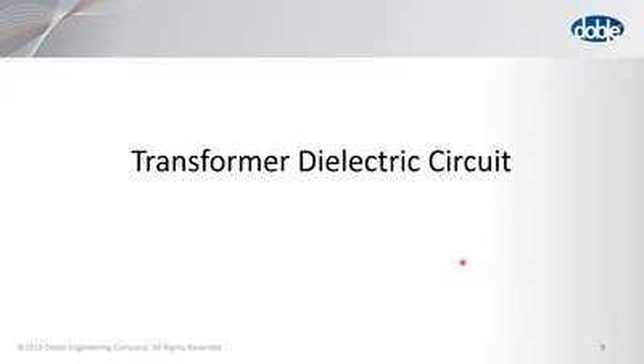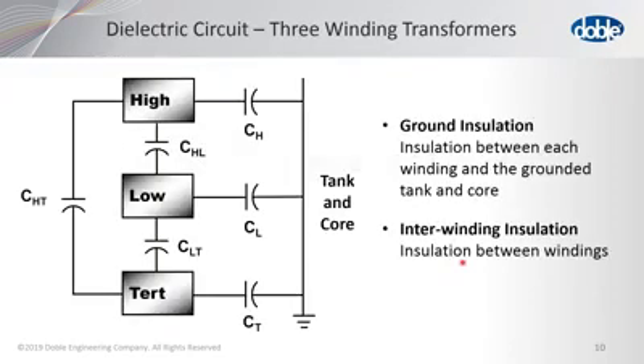So now let's look at the transformer dielectric circuit. In this particular case, we want to look at the three-winding transformer. Now, of course, there are three different windings: the high voltage, the low voltage, and the tertiary. Now, from each one of those windings to ground, that could be the grounded tank, grounded core, anything that's grounded inside of the tank, is what is going to be referenced during the test.